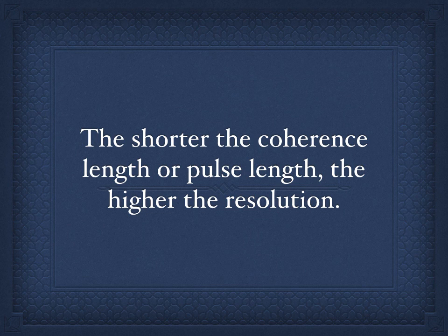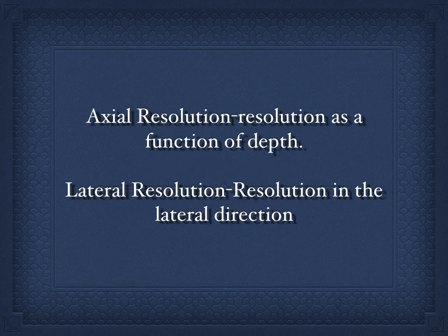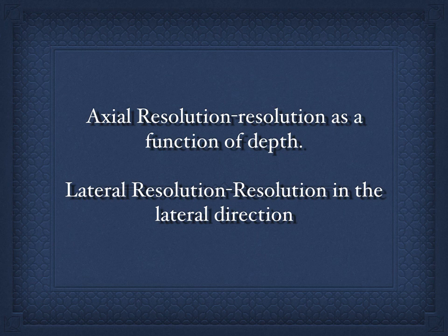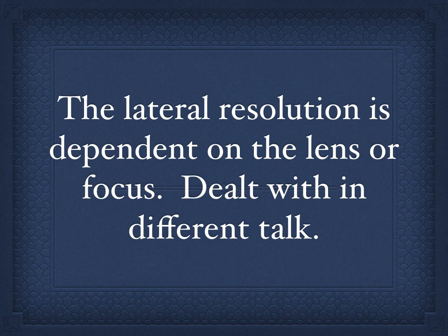The shorter the coherence length or pulse length, then the higher the resolution. When I, this resolution we're talking about right now is the axial resolution. The axial resolution is the resolution that's a function of depth going into the tissue. There's also a lateral resolution. The lateral resolution is dependent on the lenses or the ability to focus, which is different than the bandwidth dependence of the axial resolution. This will be dealt with in a different talk. It's particularly relevant to endoscopes and catheters.